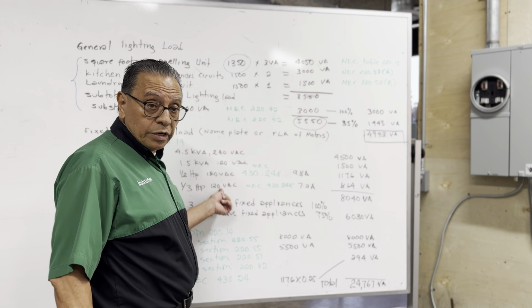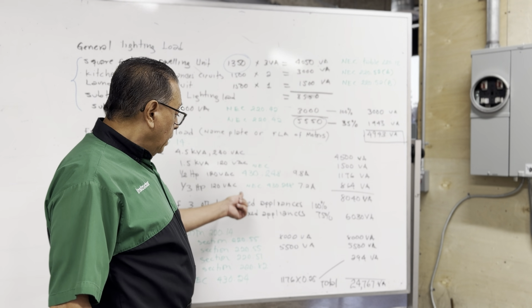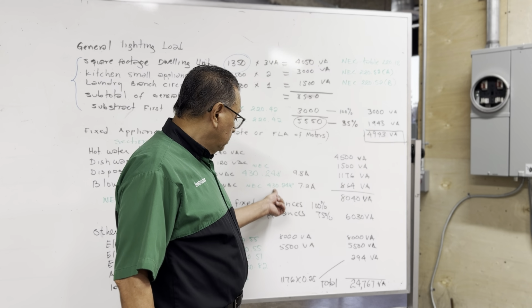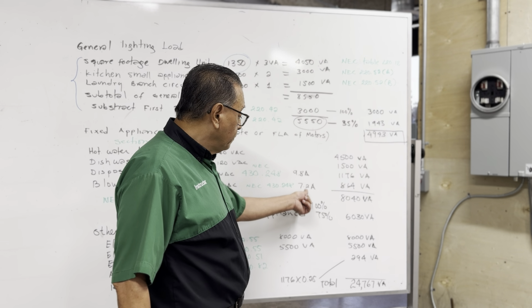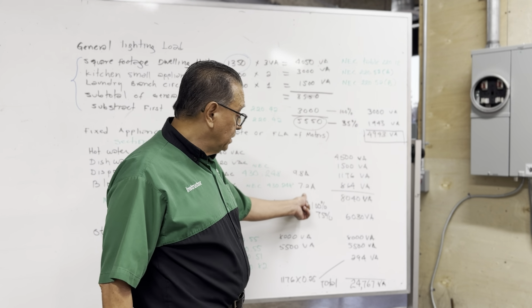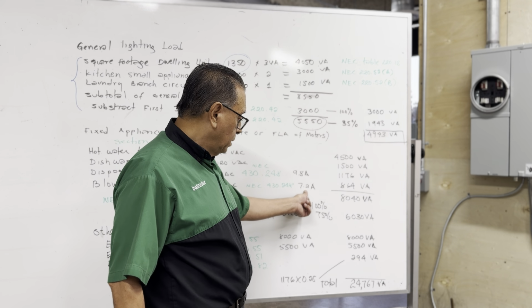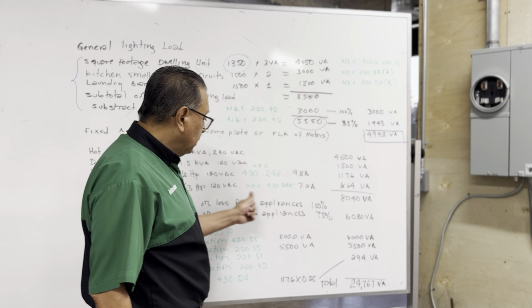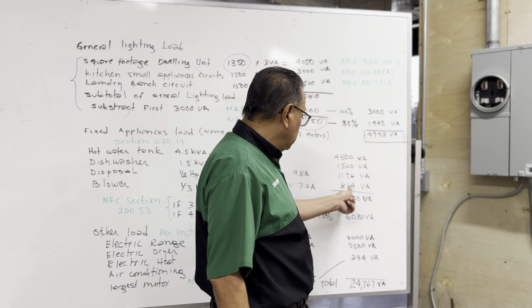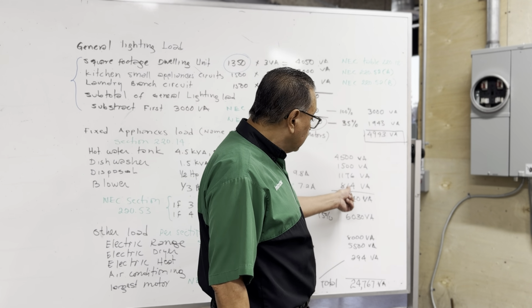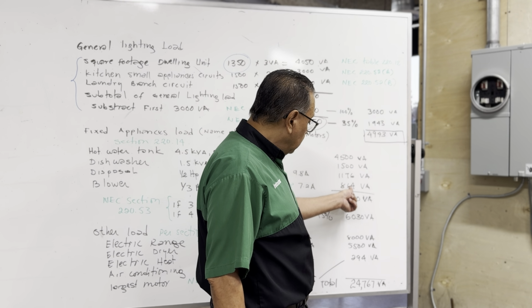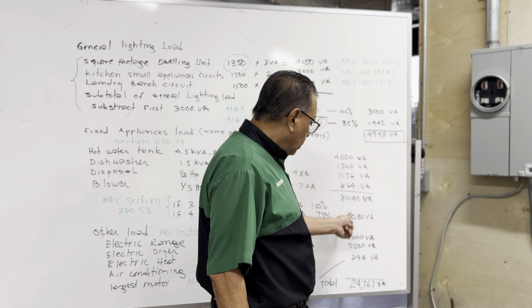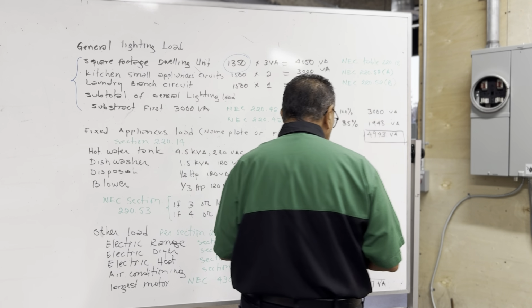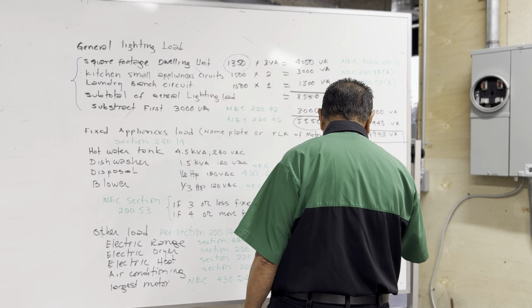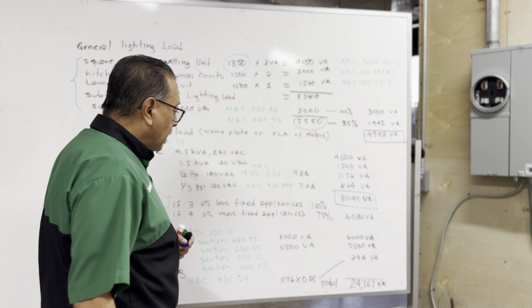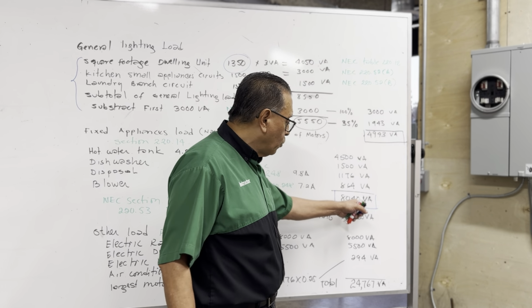For the blower, which is the motor at the top of the stove, it is a 1/3 horsepower working with 120 volts. And according to table 430.248, the full load capacity is 7.2 amperes. 120 times 7.2 amperes, I get a total of 864 volt ampere. If I add all of this, I get a total for the fixed appliances load of 8,040 volt ampere.